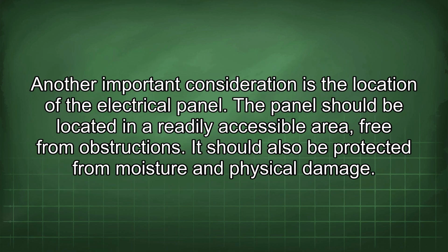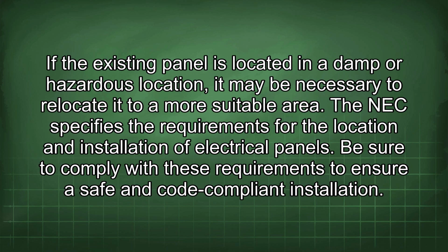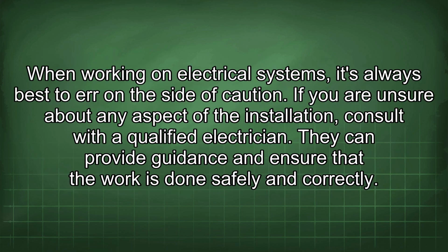Another important consideration is the location of the electrical panel. The panel should be located in a readily accessible area, free from obstructions. It should also be protected from moisture and physical damage. If the existing panel is located in a damp or hazardous location, it may be necessary to relocate it to a more suitable area. The NEC specifies the requirements for the location and installation of electrical panels. Be sure to comply with these requirements to ensure a safe and code-compliant installation. When working on electrical systems, it's always best to err on the side of caution. If you are unsure about any aspect of the installation, consult with a qualified electrician. They can provide guidance and ensure that the work is done safely and correctly.